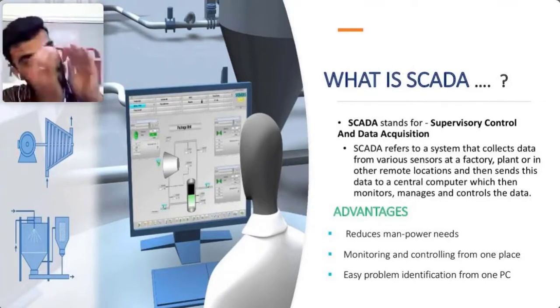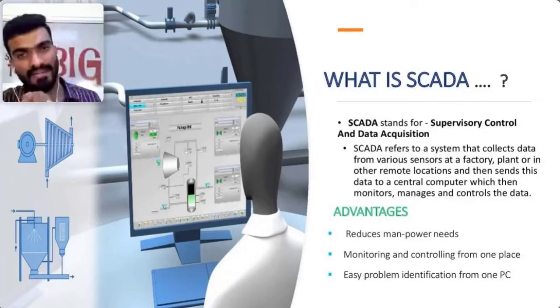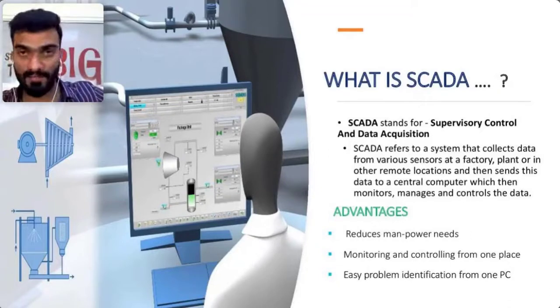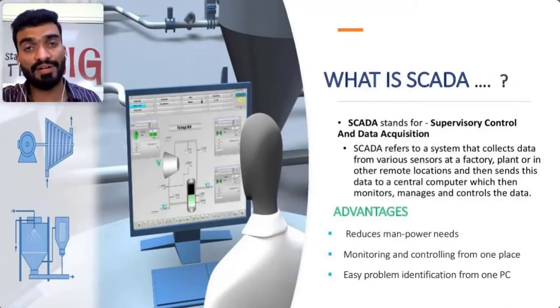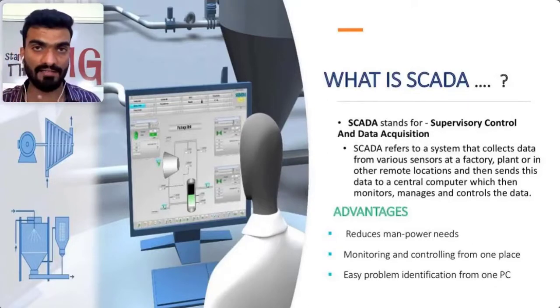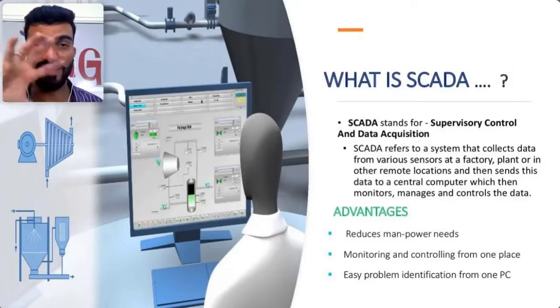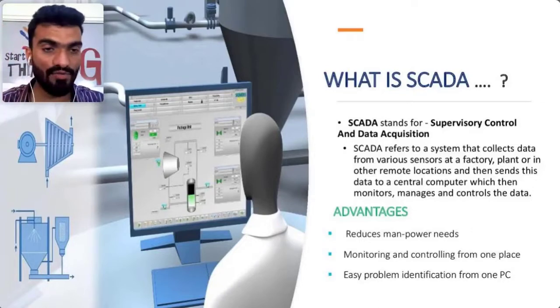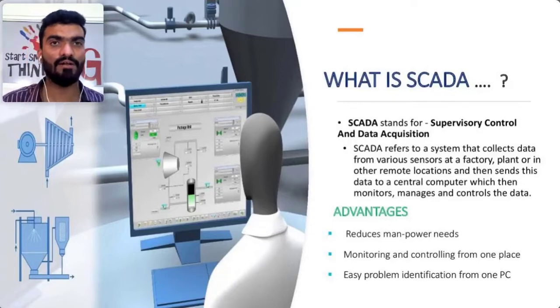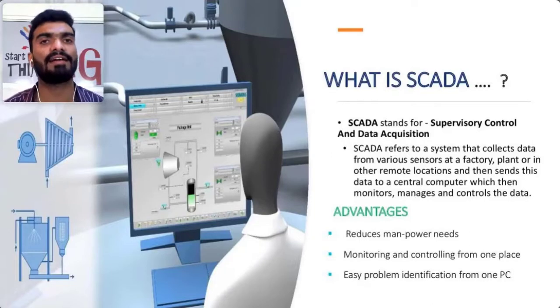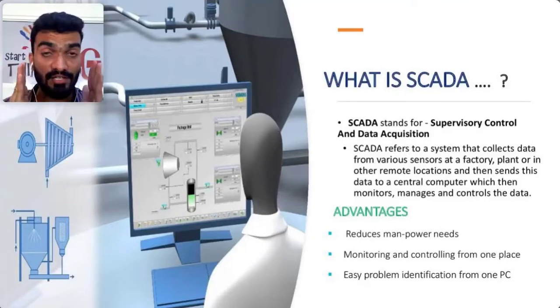When you want to see previous data, like the last 30 days of production, when the machine started or stopped, what was the production count, what was the breakdown time, everything can be checked from this history. You can generate reports, create trends, and create graphics like we've shown here, a tank with its level, a turbine, fan, pump, and so on. This is all about SCADA. You can design all these graphics in SCADA and give addressing between PLC and SCADA.